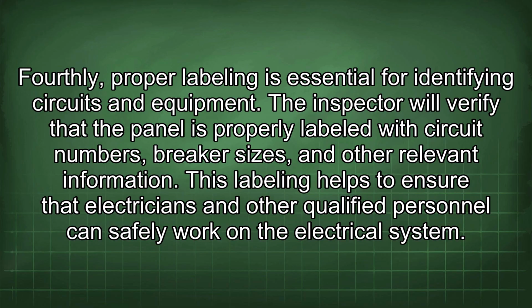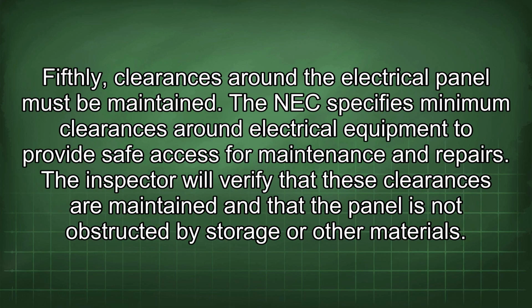The inspector will verify that the panel is properly labeled with circuit numbers, breaker sizes, and other relevant information. This labeling helps to ensure that electricians and other qualified personnel can safely work on the electrical system. Fifthly, clearances around the electrical panel must be maintained. The NEC specifies minimum clearances around electrical equipment to provide safe access for maintenance and repairs. The inspector will verify that these clearances are maintained and that the panel is not obstructed by storage or other materials.